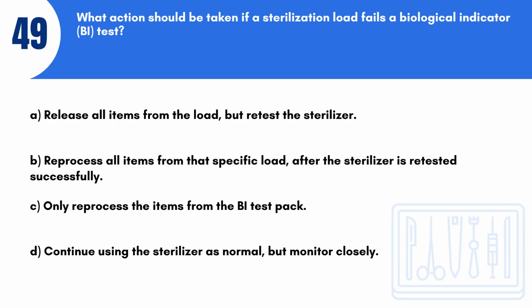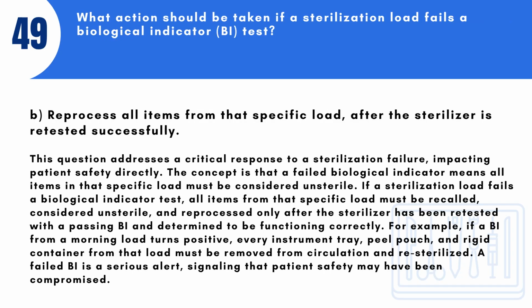Question 49. What action should be taken if a sterilization load fails a biological indicator (BI) test? A. Release all items from the load, but retest the sterilizer. B. Reprocess all items from that specific load, after the sterilizer is retested successfully. C. Only reprocess the items from the BI test pack. D. Continue using the sterilizer as normal, but monitor closely. Answer B. Reprocess all items from that specific load, after the sterilizer is retested successfully.